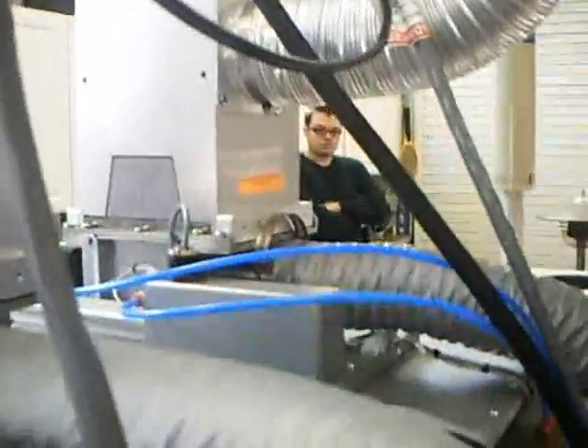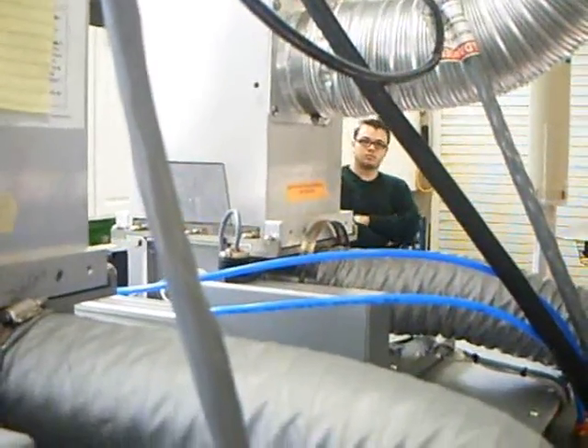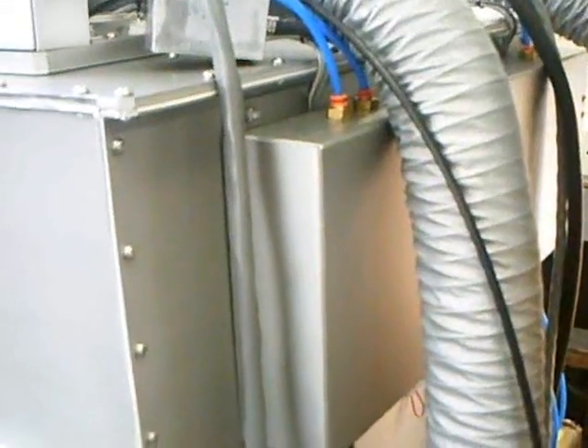This is the calibration fixture here, and you can see there's a port right there for the radiometer, and this is used for calibration only. The system is completely sealed and enclosed. It has two exhaust ports, two air inlets. This is in a laboratory environment, so the ductwork's not the best. You have one air input line and one 110 volt computer type plug as the utilities for this system.